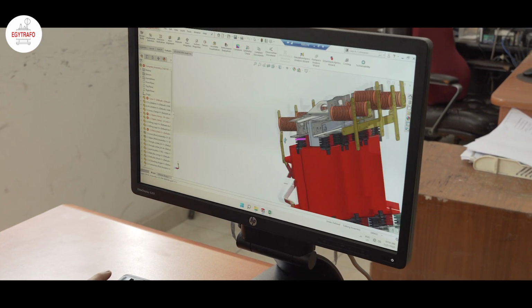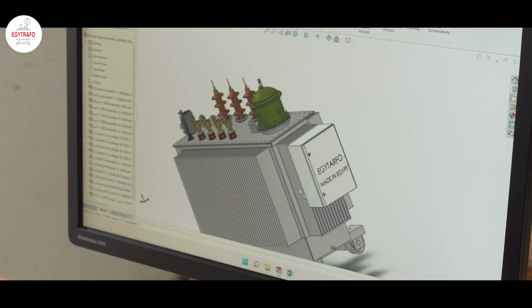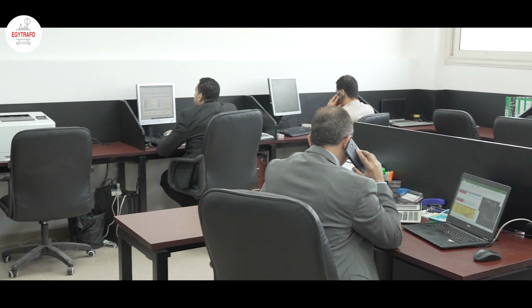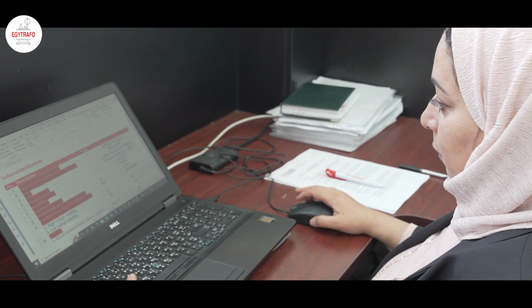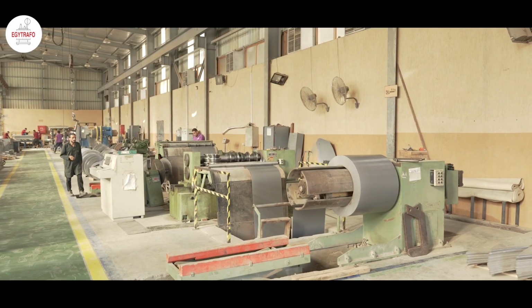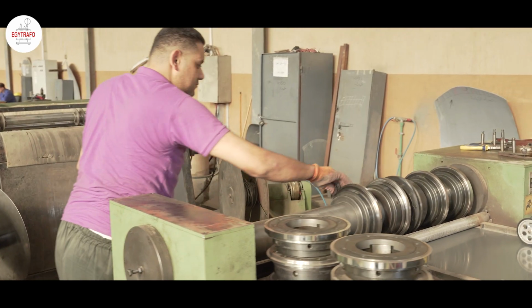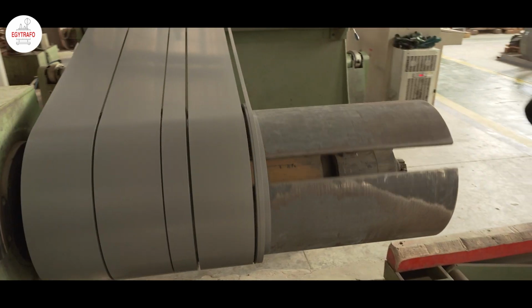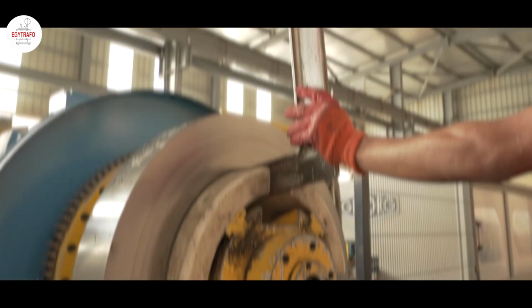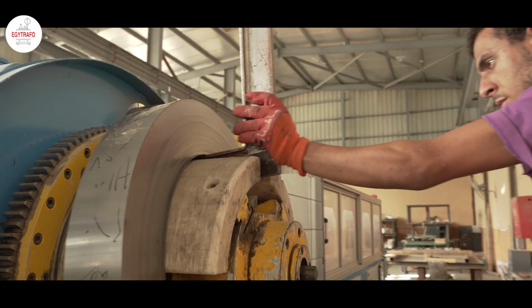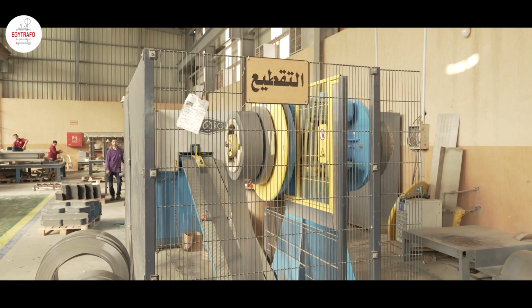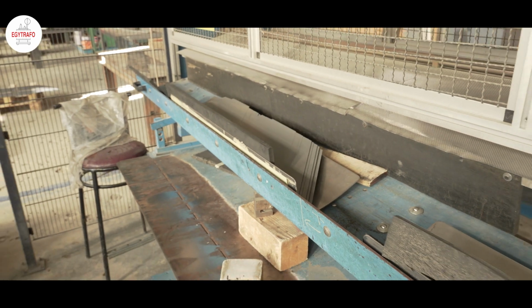Egytrafo has a very strong technical department that works at the highest level of scientific and practical craftsmanship, offering the best and most reliable products that meet our customers' requirements and demand, which are according to the latest IEC standards. Iron core. It is manufactured with first-rate, grain-oriented magnetic, cold-rolled silicon steel laminations. The core is clamped down in order to reduce vibrations and minimize noise levels. Moreover, reducing noise level and no-load losses are achieved by step-lap core construction.